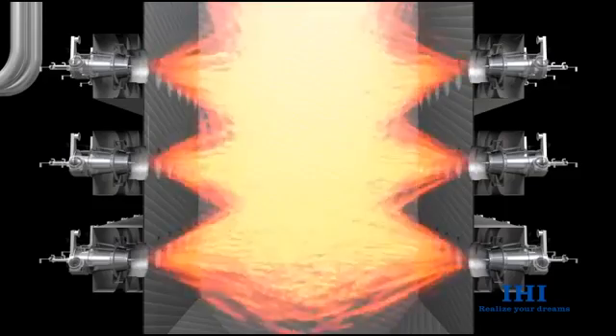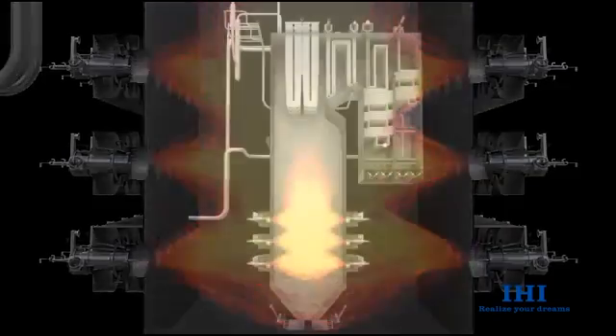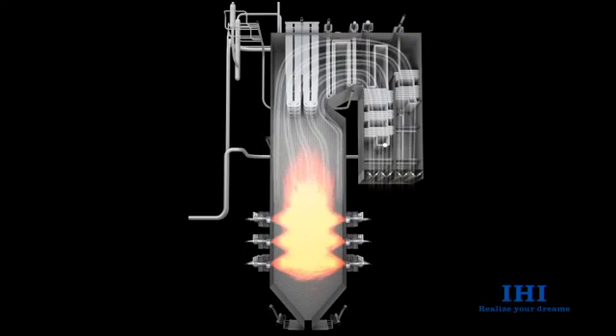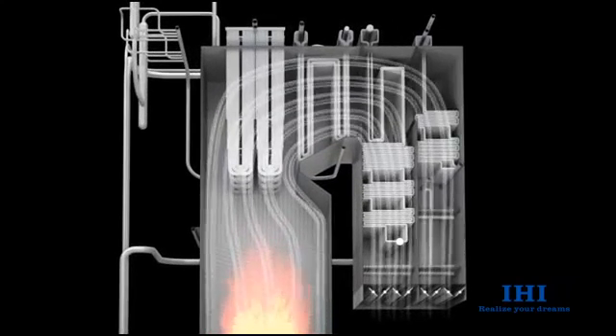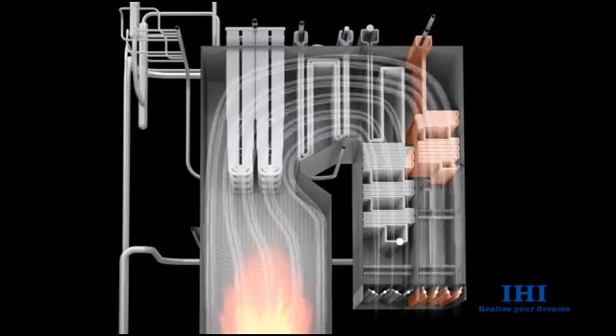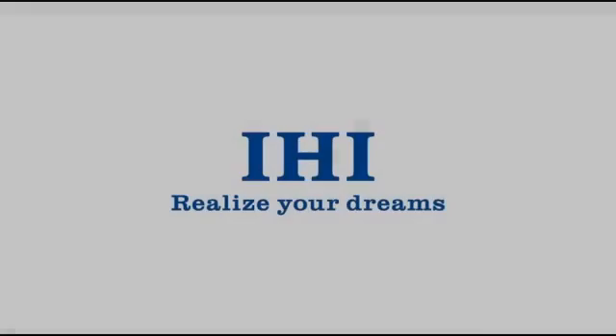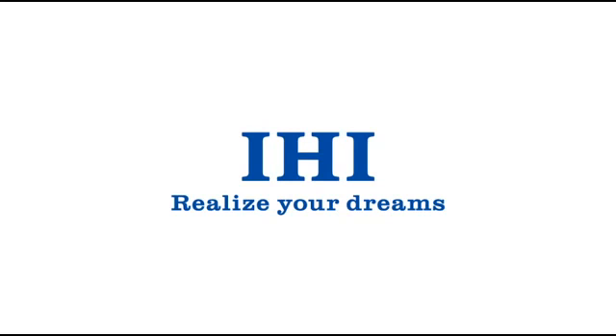The heat recovery area is divided into two separate paths by a partition wall. A reheater is installed in the front side and a primary superheater in the rear side. To control the reheat steam temperature, the combustion gas flow rate in both paths can be controlled by the damper installed at the bottom of the heat recovery area. This is called the parallel path method, which increases efficiency compared to steam temperature controlled by a spray attemperator.